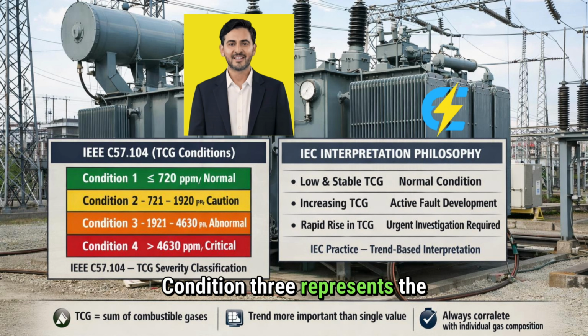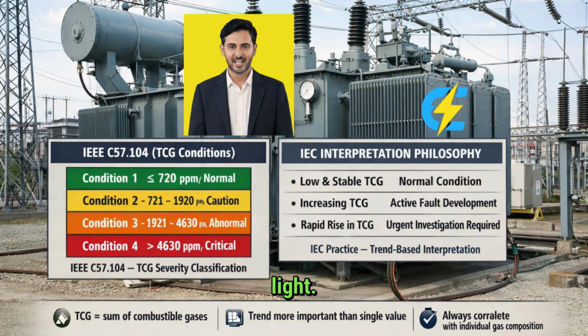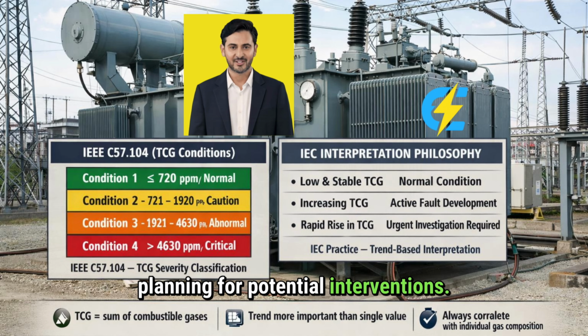Condition 3 represents the high range with TCG between 1920 and 4630 parts per million. At this level, a fault or faults are probably present. You need to take DGA samples frequently enough to calculate the amount of gas generation per day for each gas. This is your orange light. Action is required and you need to start planning for potential interventions.